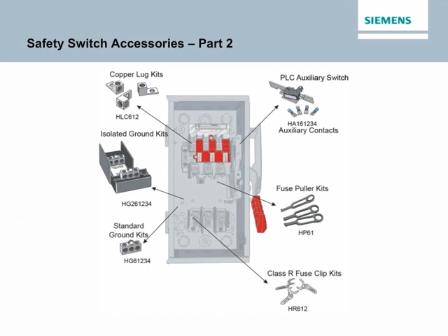Fuse puller kits are field installable in 30 to 100 amp heavy duty switches. Class R fuse clips are used to prevent the installation of non-current limiting Class H or Class K fuses. All general and 30 to 600 amp heavy-duty switches are field convertible to accept Class R fuse clip kits.